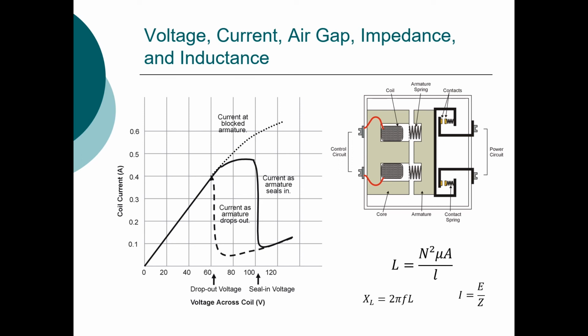We see the same type of effect happening as we reduce our voltage going to our coil. As my voltage gets to my dropout point, what we'll find is as the armature opens up and I gain that air gap back, it is also reducing my inductive reactance, which will increase the current going through my coil again. So we can see this action between the current and the voltage and whether or not that core is open or closed and the inductive reactance within it.